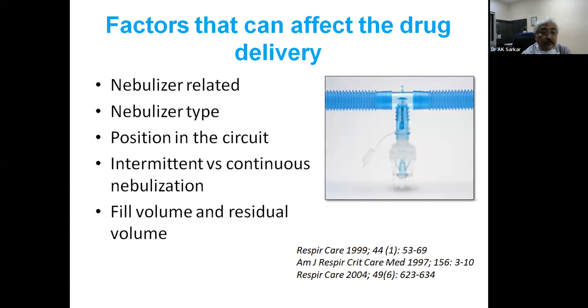Most of our units have been using jet nebulizers before, but currently we have started using mesh nebulizers. Most of the time, a jet nebulizer is less efficient than an ultrasonic or mesh nebulizer, because in a jet nebulizer the particle size will always be above 5 microns, and most of the particles or aerosols deposit within the tubes, and very little of them go to the bronchial or alveolar level.